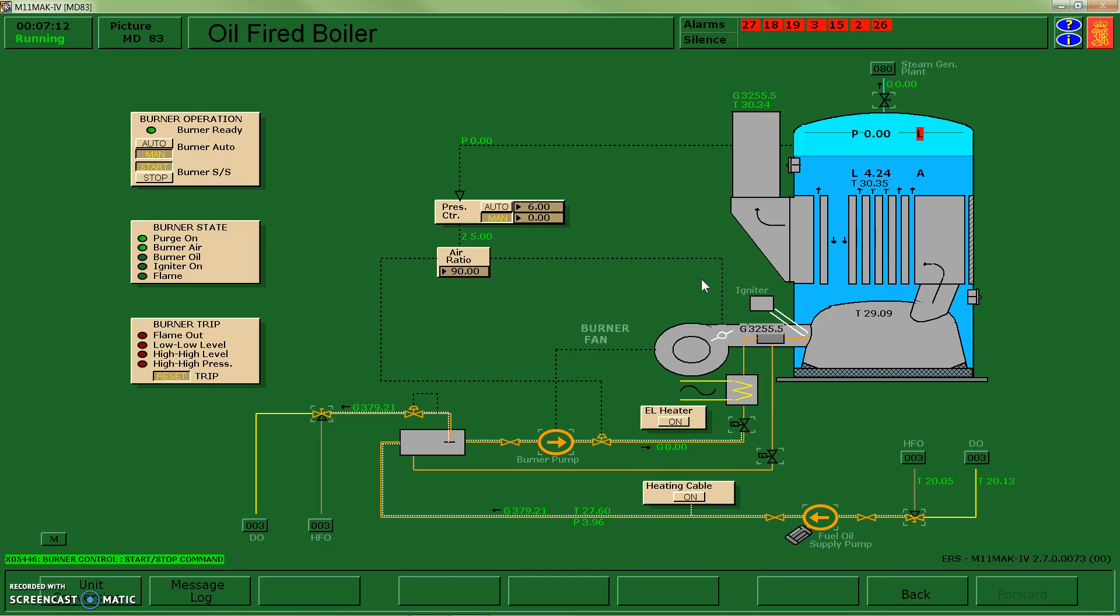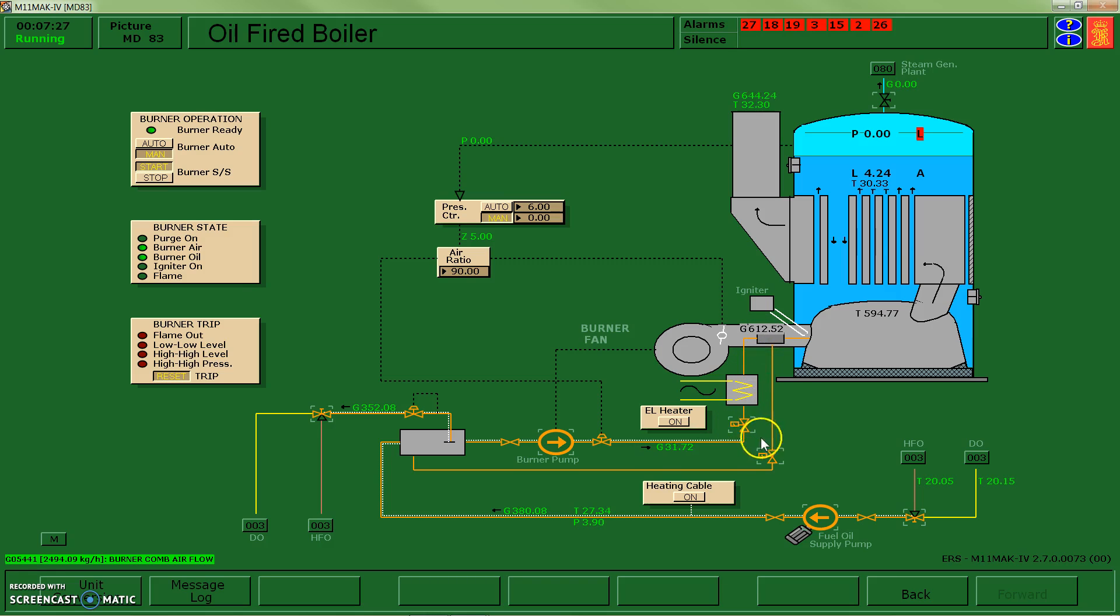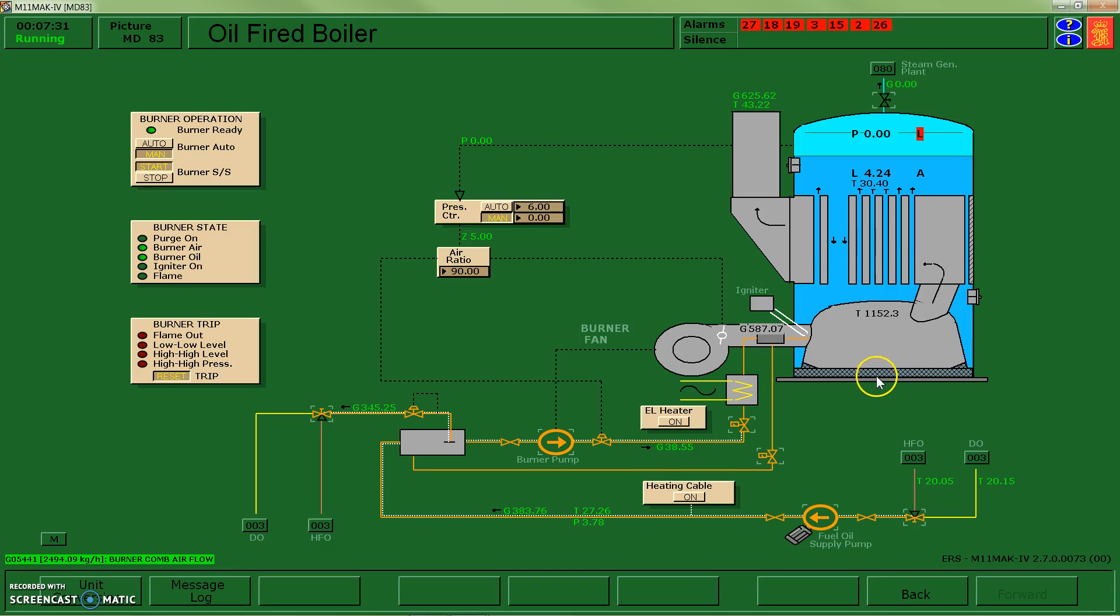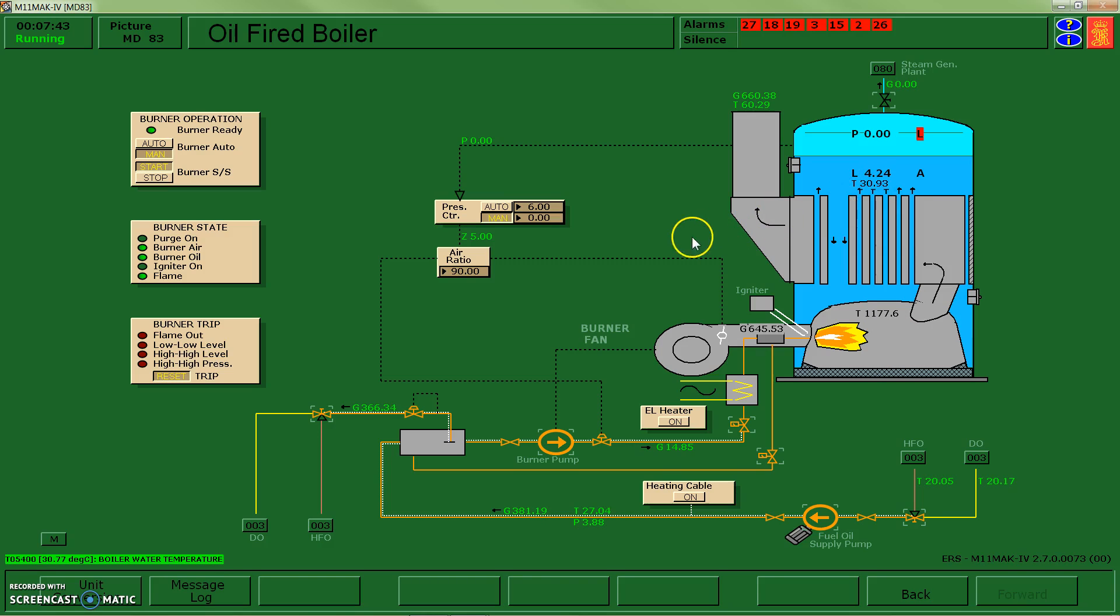So I'm going through my purge, I'm blasting through a large quantity of air. You can see over here my purge is on. My airflow just got reduced, and now my fuel valve's opened up and I've started my main flame with the igniter on. I've now validated that my flame is functioning, and you can see that the temperature is starting to rise in the boiler.